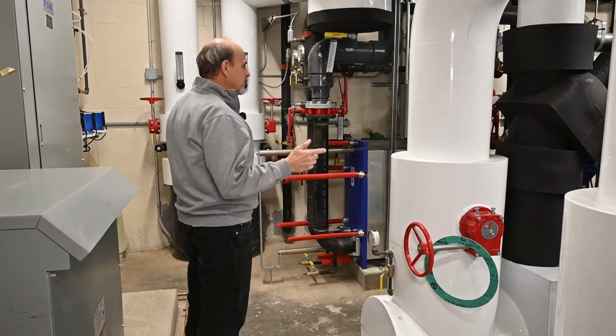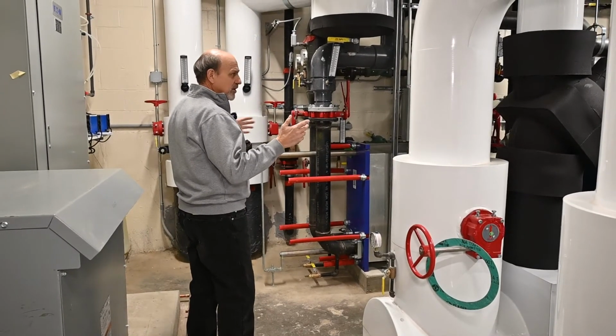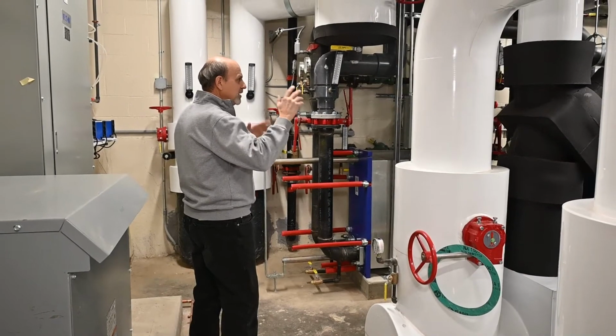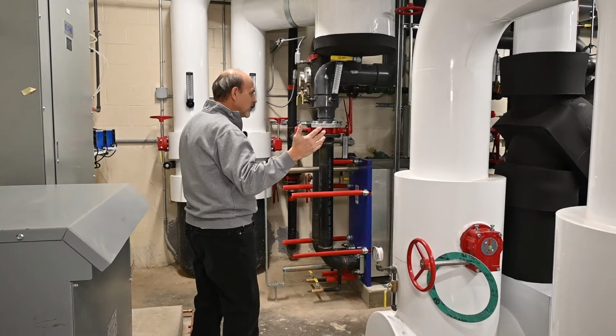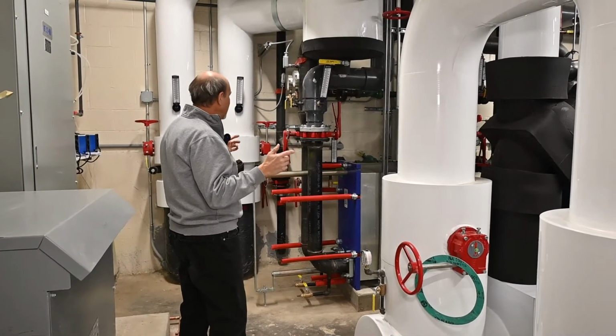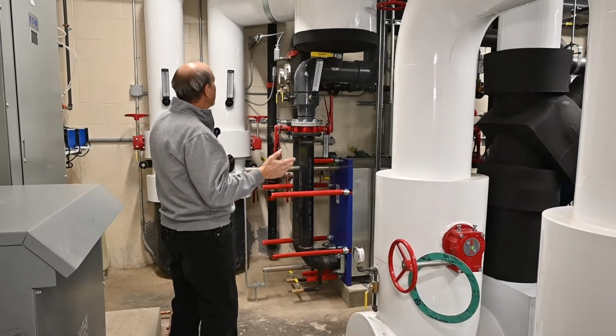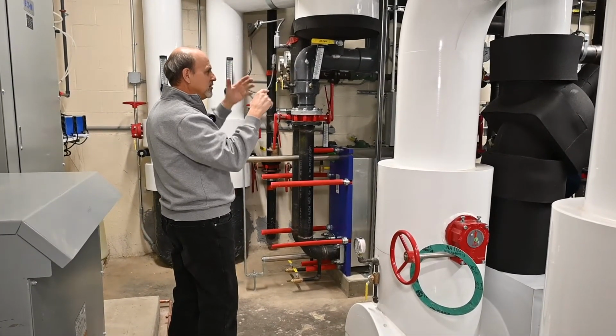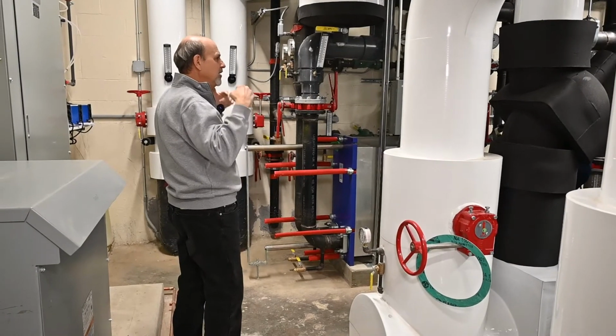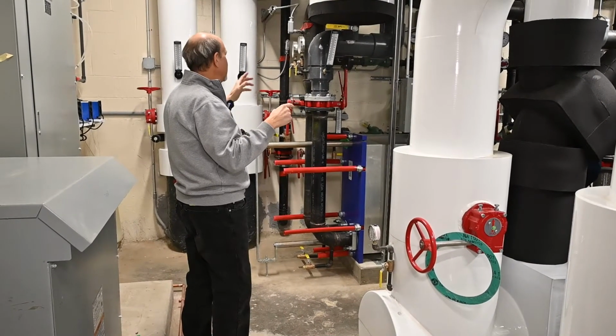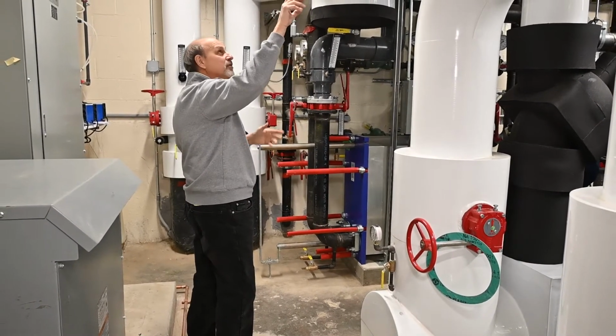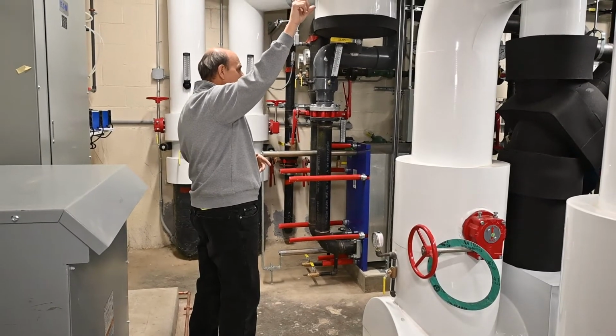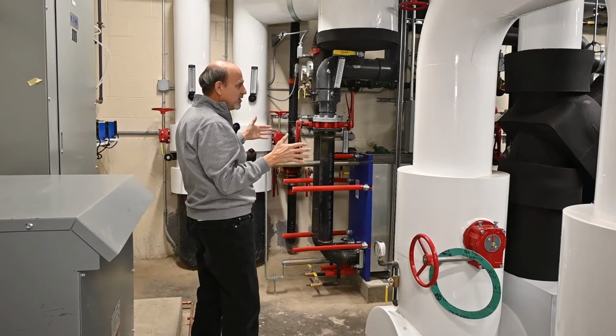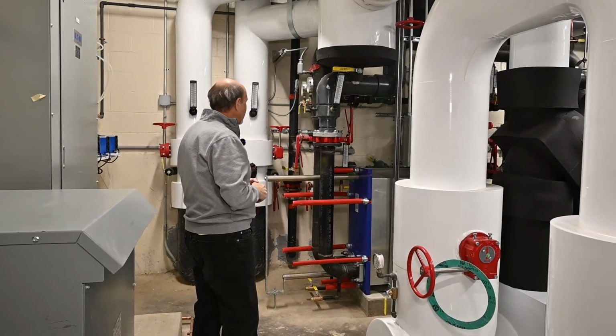So we're here at the rink, and basically I just wanted to go over the piping systems and valving and things of how we built this boiler room and understand the flows. Before I'm done with this project, all of these pipes are going to be labeled with what they are: glycol supply, glycol return, flow arrows, different sensors that Carl and I installed. We're going to put sensor numbers on them that all correspond to the as-built drawings from an electrical standpoint.